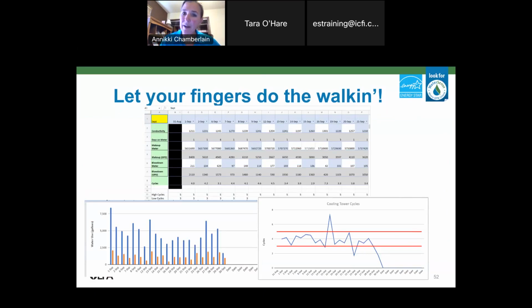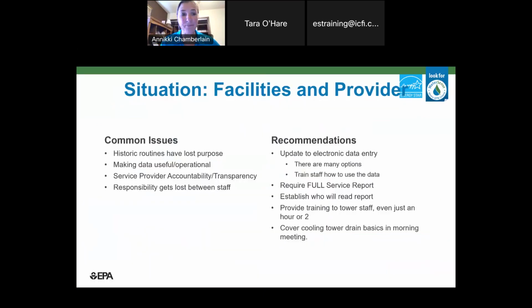Basically, setting up, I like to use Google Sheets because it allows people to enter information in the field. I can fix it from a distance, but as we're entering our makeup and our blowdown, it's automatically calculating the water use and the cycles of concentration visually. So I can see right away, oh man, do I have a problem or do I not? So again, require full service reports. See if you can update any data management into electronic, where it's automatically calculating those meter reads.